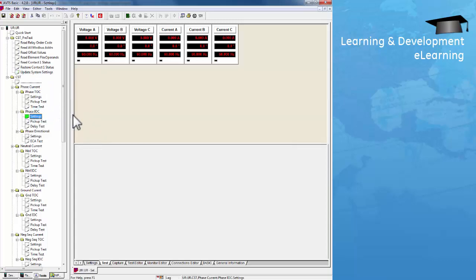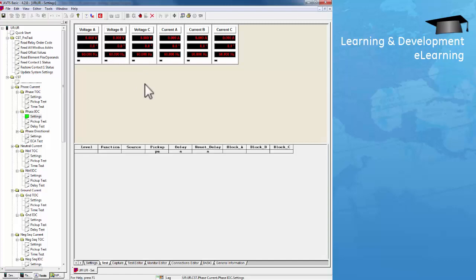Next, I'm going to run a phase IOC pickup test. First, I'm going to read the settings of this phase IOC. This shows IOC1 is enabled — the mode and pickup settings with 1PU block set to virtual input 1.